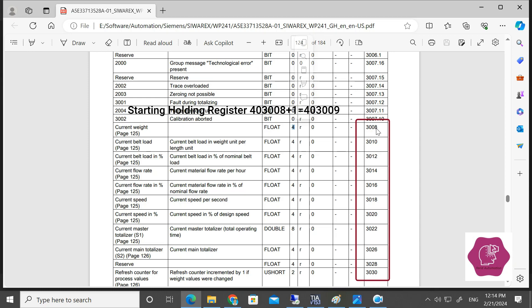But for the PLC, it will be 3009 — we have to add one to that holding register. So our starting address will be 403009, and we will take 1 through 10 registers — or actually 9 or 10 data, meaning 9 or 10 double words for floating. Each holding register has 1 word, so each data will take 2 words, which means 1 double word.